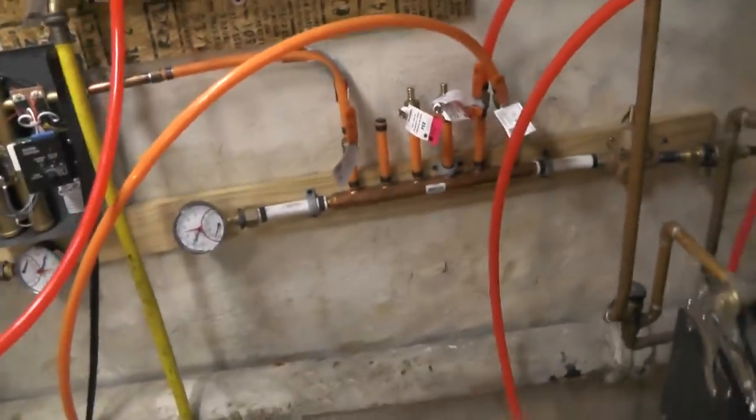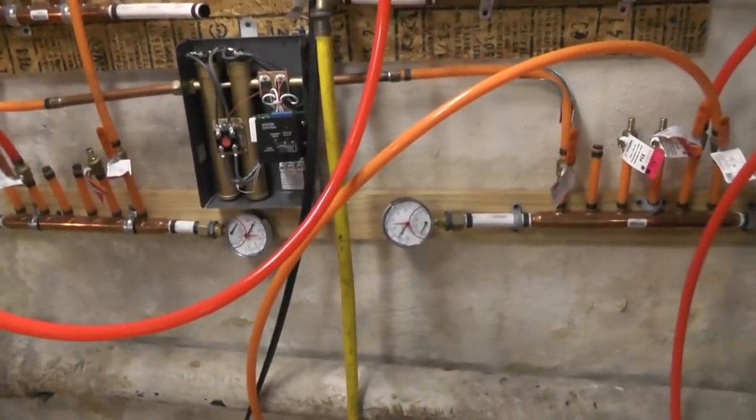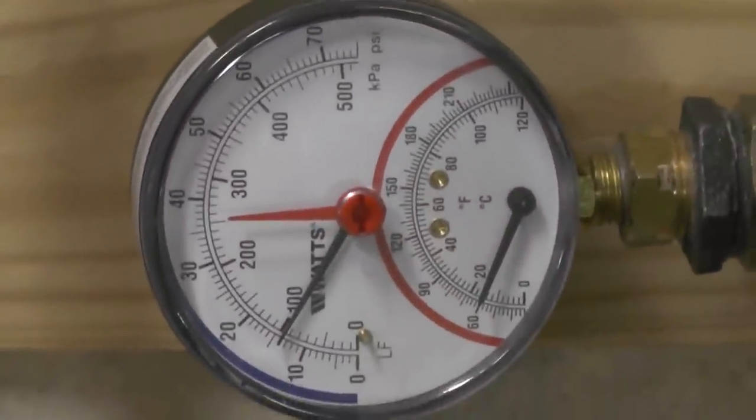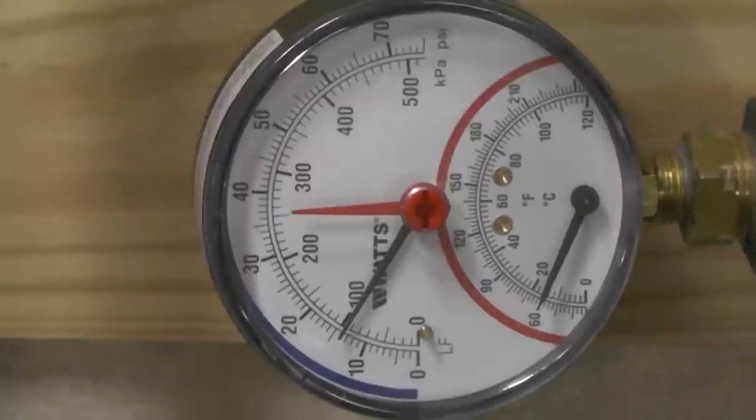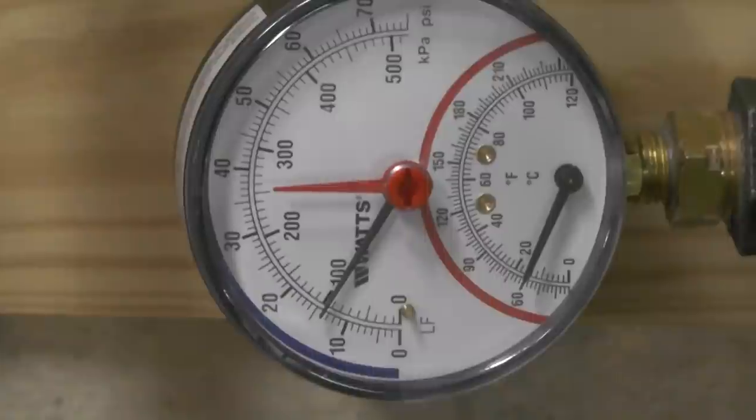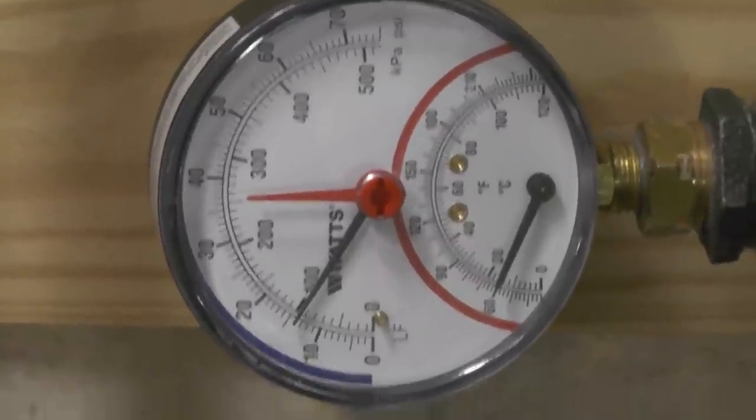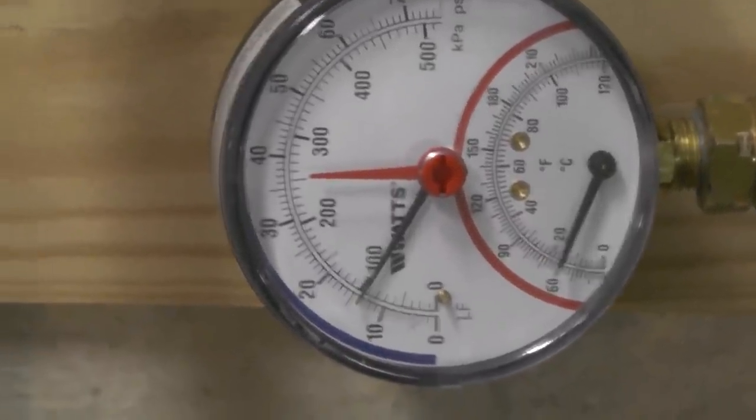And so I'll go over the gauges real quick. This is measuring the return water so right now the system shut down, it's not working, so it's why it's showing about 60 degrees and it runs usually around 12 psi. Right now it's sitting static at 14.